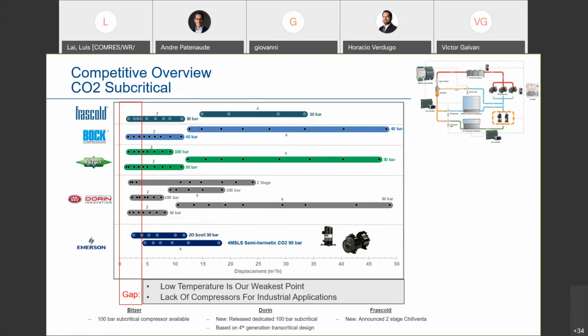So you get a little bit of cycling going on with that compressor. That's why our competitors do have some smaller displacement models to handle those smaller loads. And not just from a supermarket perspective, but the refrigeration architectures in transcritical and subcritical are becoming smaller and smaller capacities as customers try to move closer and closer to an all-natural refrigeration solution.